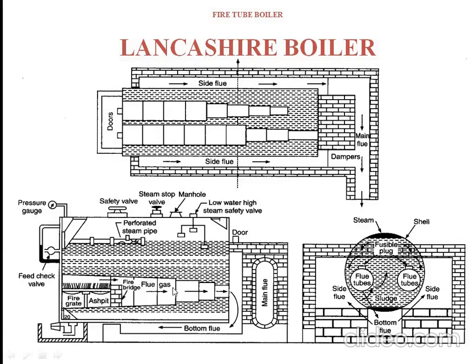If you see the cross section of this tube, it is conical towards the front — the area is decreasing from here to here. If the area decreases, velocity will increase; therefore it accelerates the flow of the flue gases. The flue gases start from the grate and move towards the forward direction. Again, through the downward channel, they go to the bottom flue. From the bottom flue, the flue gases pass through the front again.